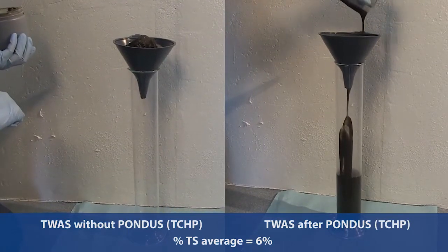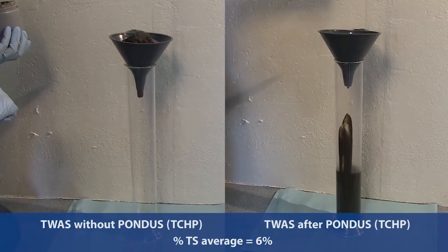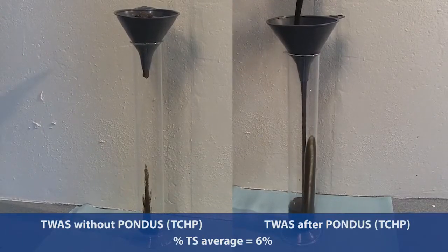So I think the advent of PONDUS is really governed by more anaerobic digesters being in operation in Germany, and the higher electricity prices. So here we see really drivers, definitely disposal costs, but you also see some digester retention, digester capacity issues. If you implement the PONDUS hydrolysis, you can feed more solids to your digester or reduce the detention time in the digesters, meaning your plant creates more capacity to operate with the existing investment they have, and process more waste through the system.